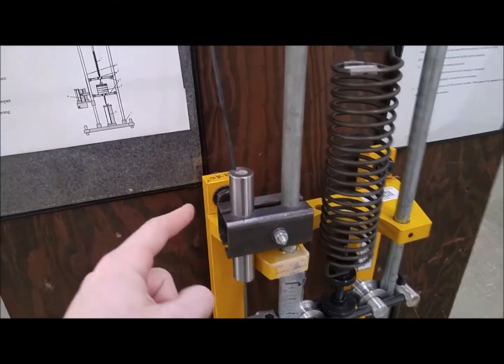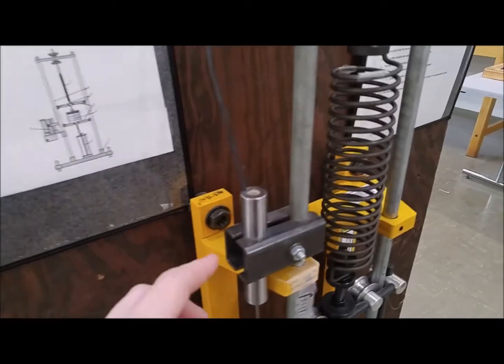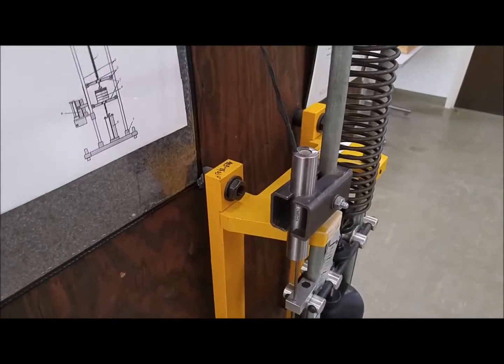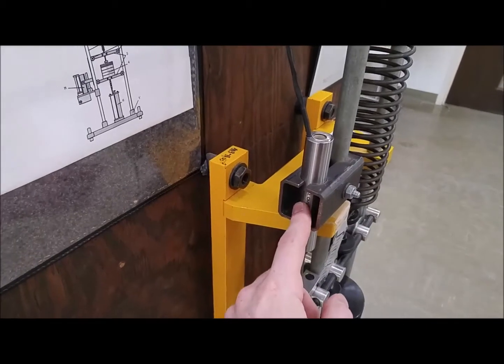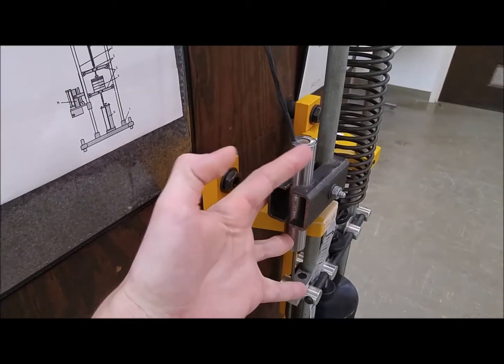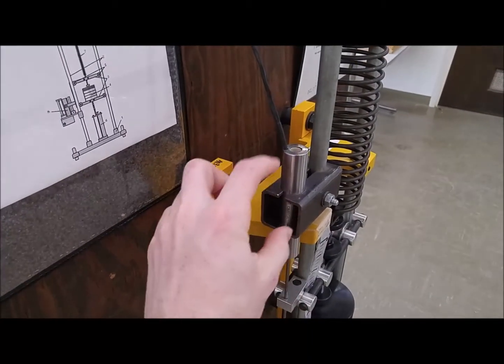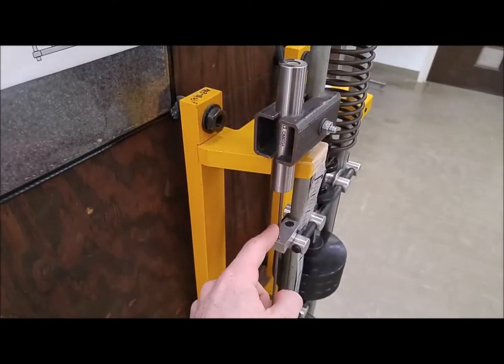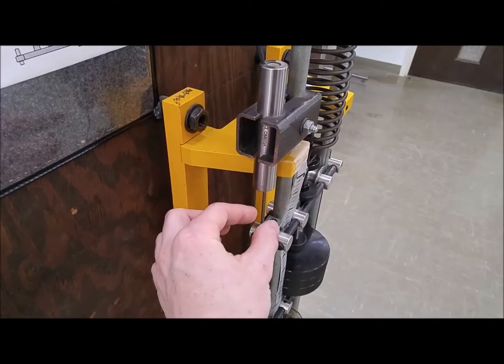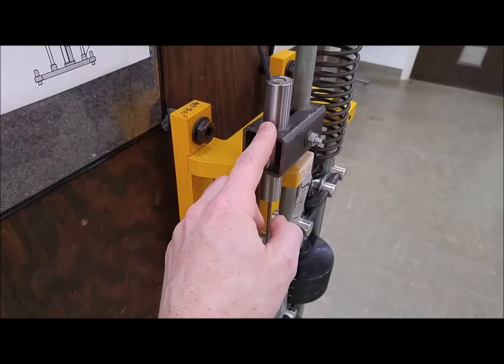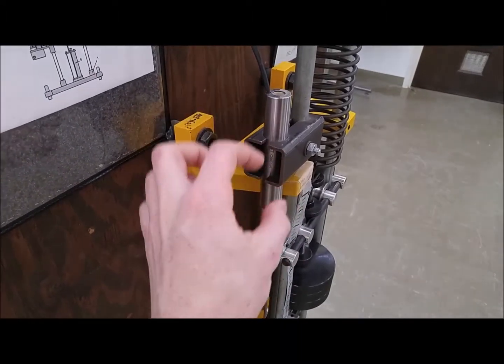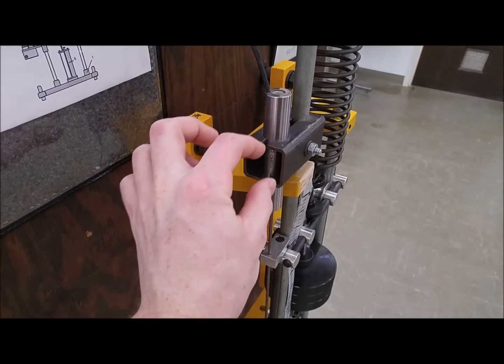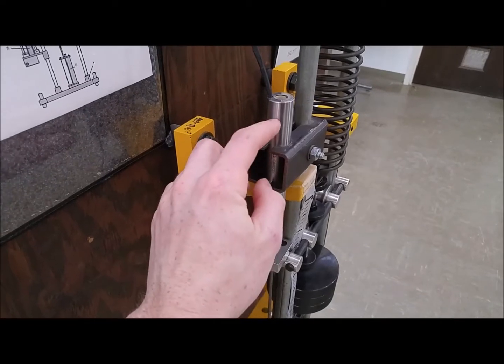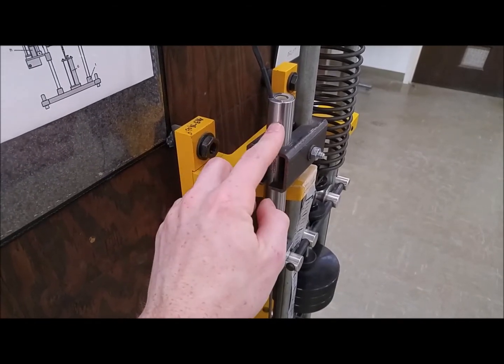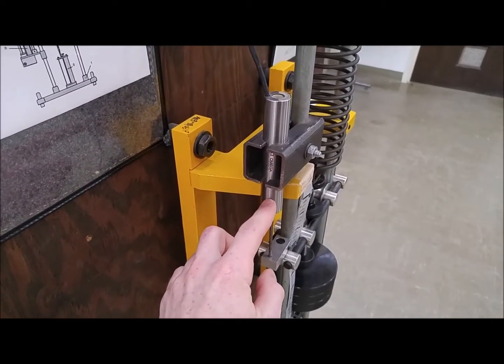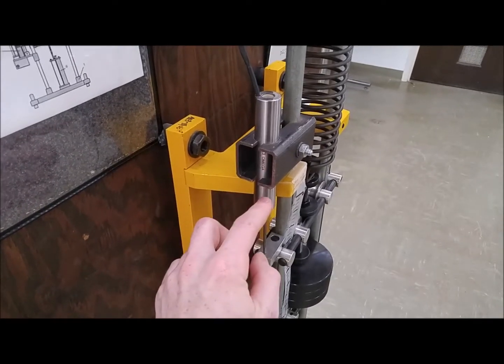So this is a linear variable differential transformer, or LVDT. So basically there's a main coil in the middle here, and then two coils on either side, there and there. So based on how far this conductive, I think it's iron or steel, rod moves up and down inside there, you have a voltage difference. So the currents are intersecting. So if the rod is further on this side, you'll have a positive or negative voltage. If it's further on this side, it's vice versa.